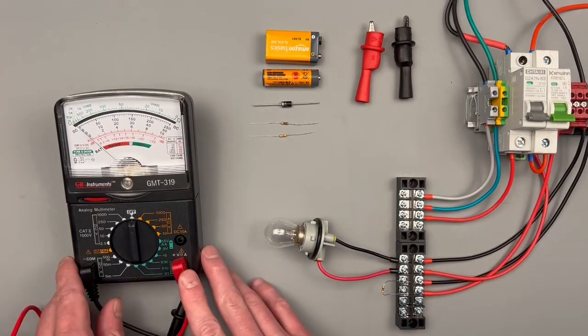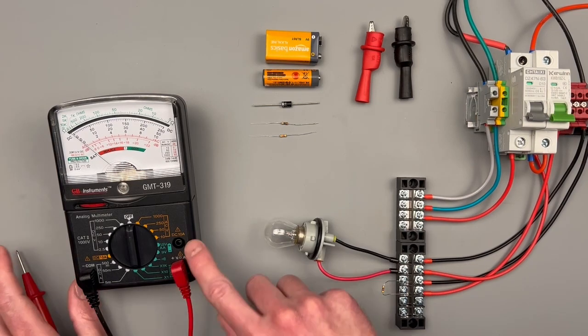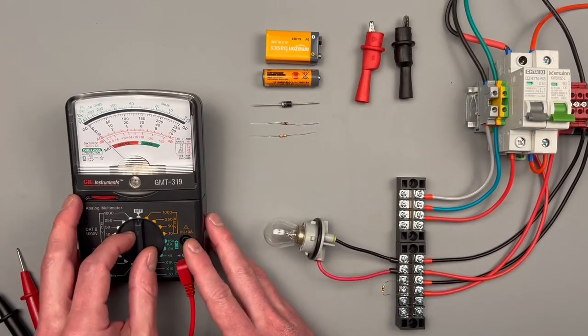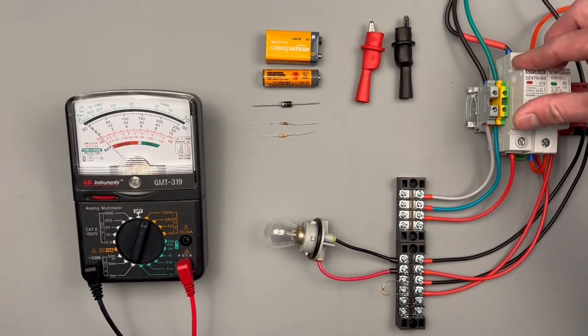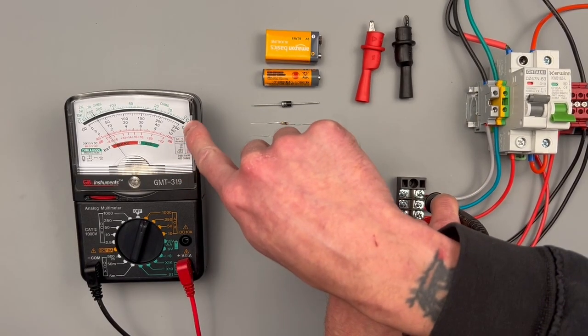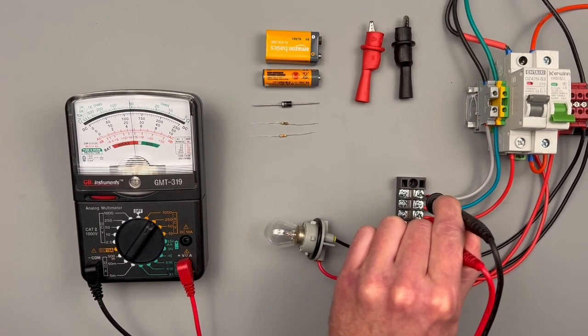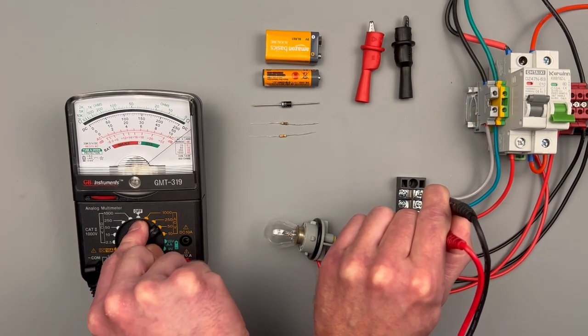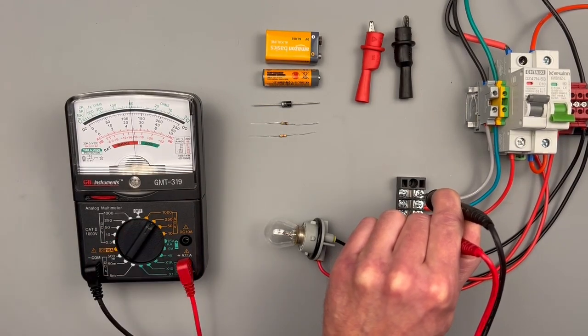Let's start with volts AC. Take note of your probe positions when doing these measurements. The only time you're going to need to switch over your hot probe to this port is going to be for measuring DC current. I'm going to start with 120 volts AC at the thousand volt scale and see what that looks like. This measurement's done in parallel. So you can see there is no thousand volt scale on the meter. That's kind of frustrating. You'll want to put it to the 250 scale and here we can see that we're reading 120 volts. I'm looking here at this first row in these black numbers to get my reading. If I do bring my scaling down to the 50, you see that needle is just pegged out. It's telling you that it's out of range.